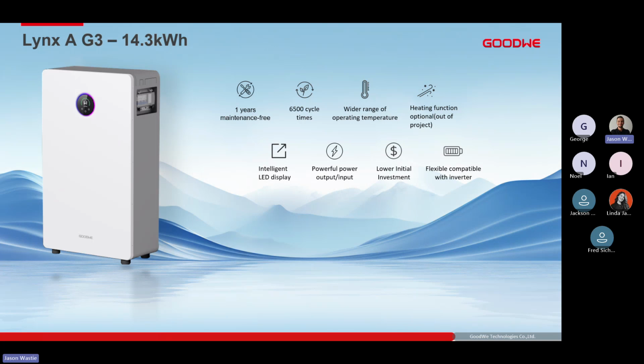So the next part of the session is to have a look at our Lynx AG3 14.3 kilowatt hour battery. This will be phased out and replaced by our 16 kilowatt hour battery that will be coming soon. However, right now we have got the 14.3 kilowatt hour battery available. So this is a more enclosed battery. It's not a normal rack mount battery like our 5 kilowatt hour battery. This is a much bigger unit, and we can either have it floor mounted or wall mounted. We have got an intelligent LED display on the front of it with some light diagnosis to tell us exactly what is going on with the battery, as well as a built-in circuit breaker on the right-hand side of the battery as well.